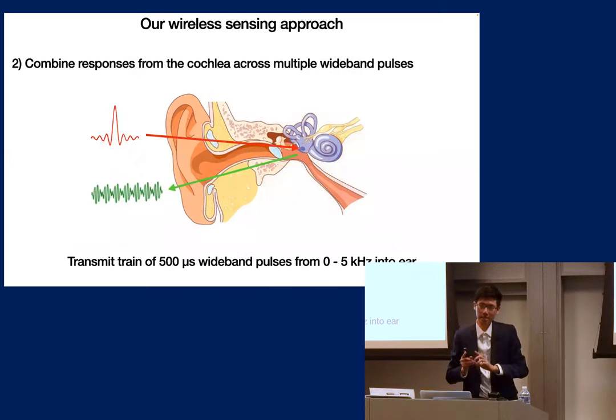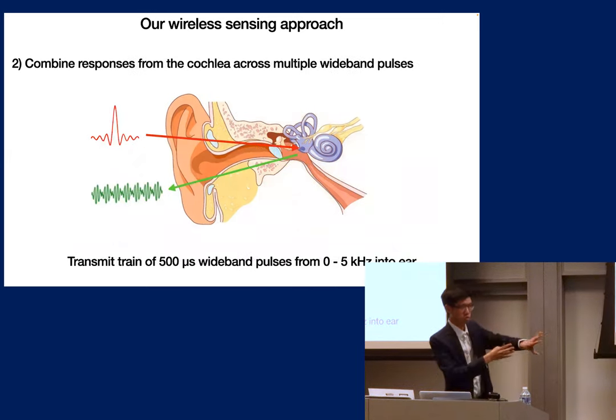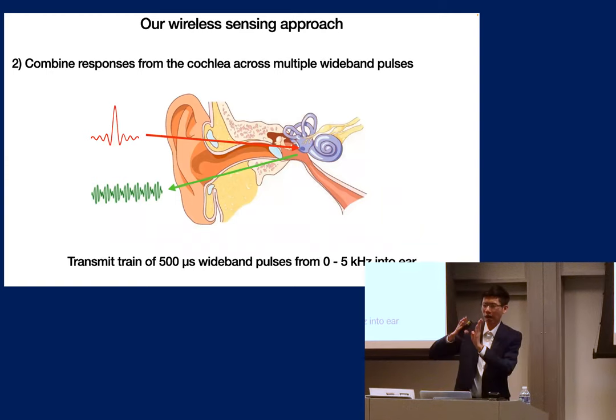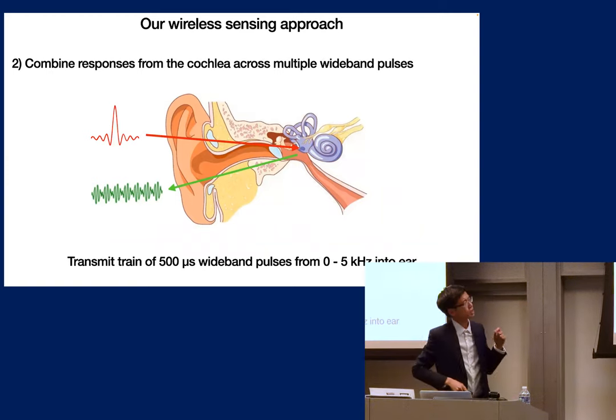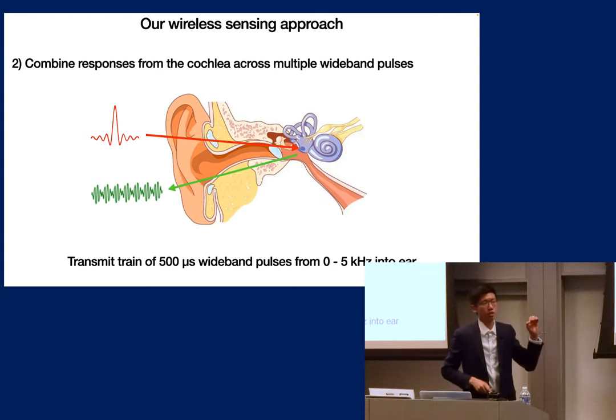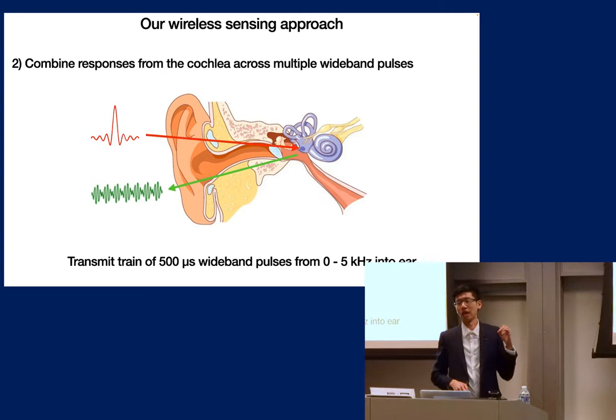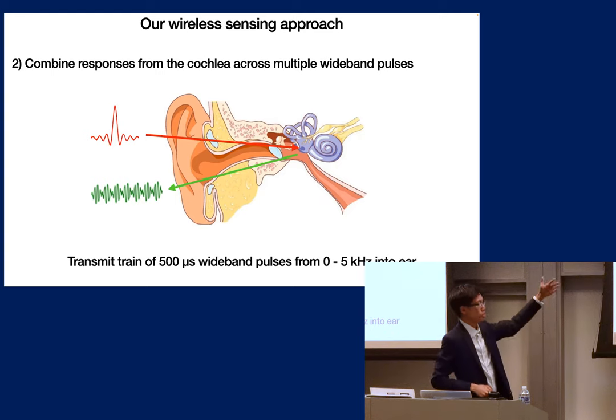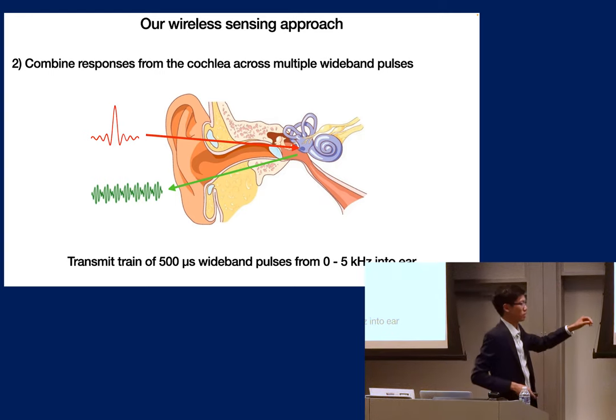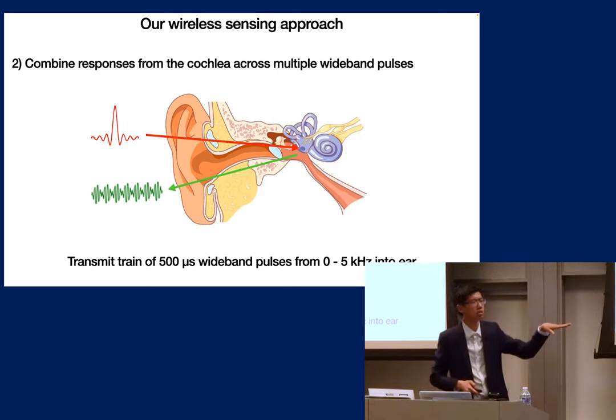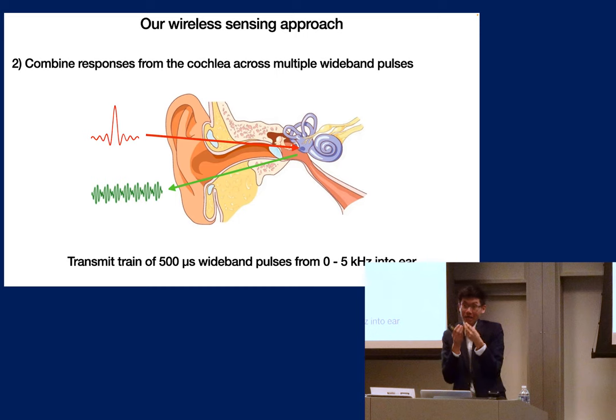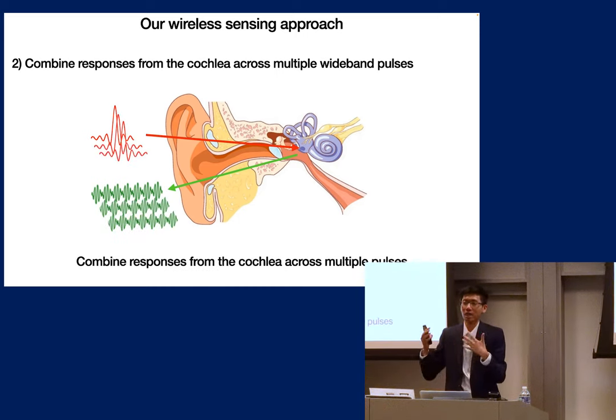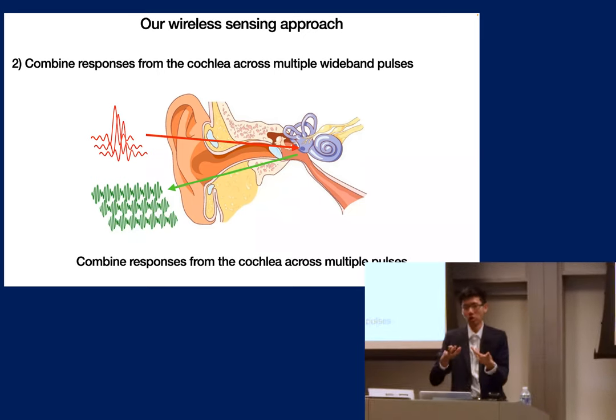That brings us to the second step, where you ignore that previous duration where reflections occur and look at what's after that time delay. Here, the goal is to elicit responses from the cochlea. To do that, we don't send a chirp, we send a wide band pulse from 0 to 5 kilohertz, 500 microseconds in size, into the ear. What comes back is a very low amplitude signal, but you can combine responses over time to boost the signal-to-noise ratio and detect these signals robustly in the ear.